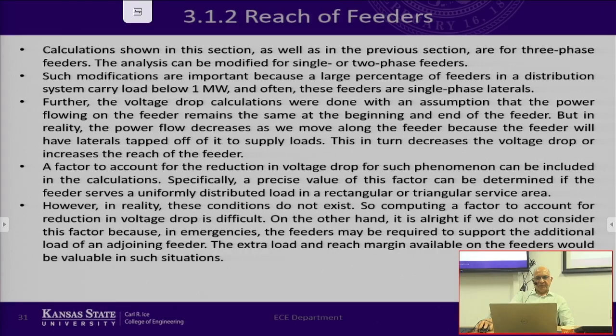The voltage drop calculations were done assuming the power flowing on the feeders remains the same at the beginning and end of the feeder, but in reality power flow decreases as we move along the feeder because the feeder has lateral taps. So this is an approximation, assuming the feeder has the same load throughout.